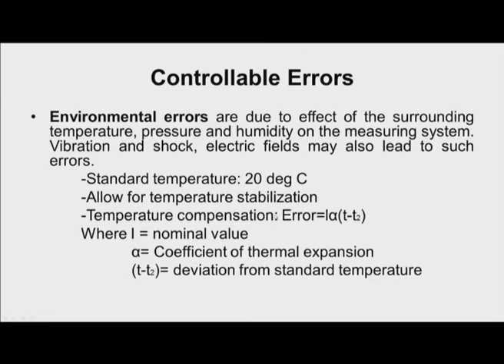Now, if we have two different kinds of materials, then the error can be calculated using this relationship: L times (alpha 1 minus alpha 2) times (T minus T2), where alpha 1 is the coefficient of thermal expansion of the first material and alpha 2 is the coefficient of expansion for the second material. Measurement error may also be due to improper datum surface, which we discussed already, and maybe the presence of dirt and chips. Due to this also the measurement error may creep in. That means we need to clean the datum surface properly, so that there is no dirt or chip. We can understand this by a simple diagram. Say there is a dust particle or dirt particle, and then if we place the instrument like this, then this much error will be introduced. So, we should clean the datum surface and then go for the measurement process.